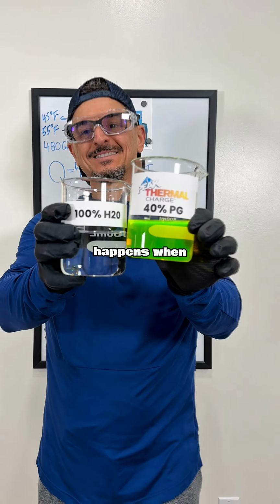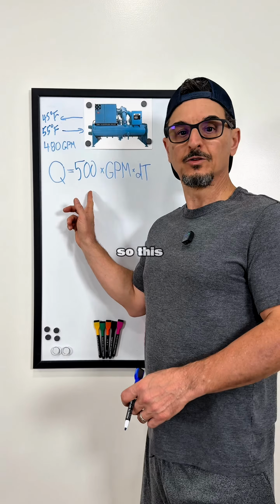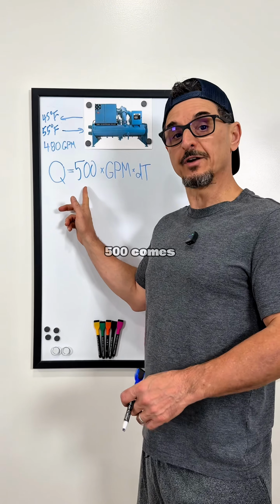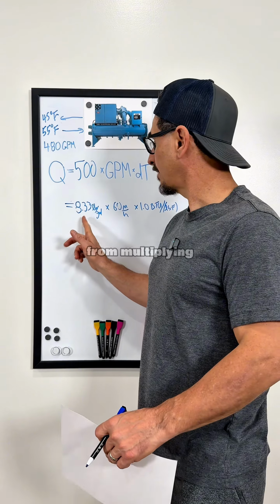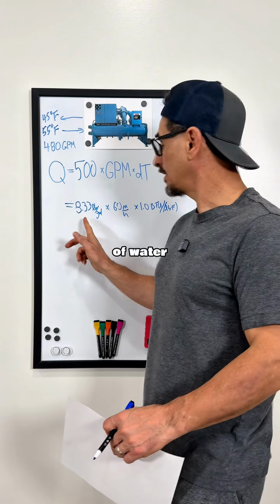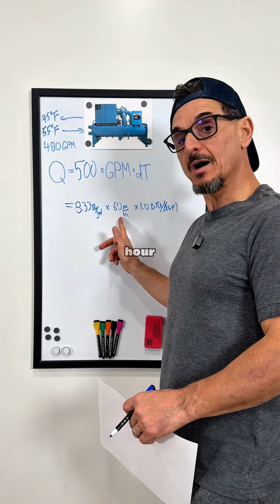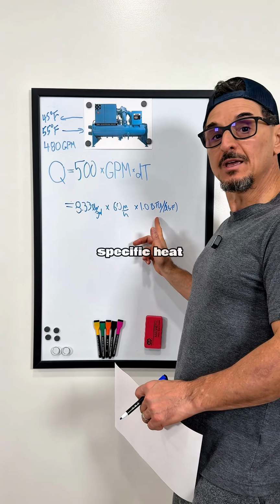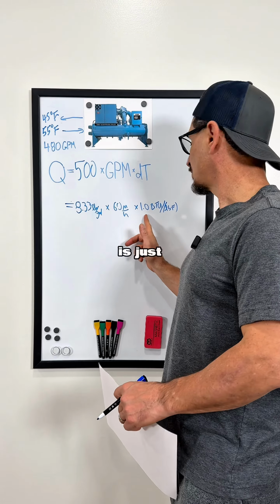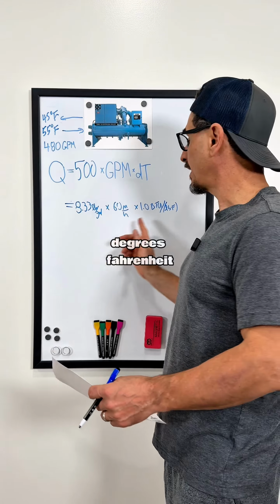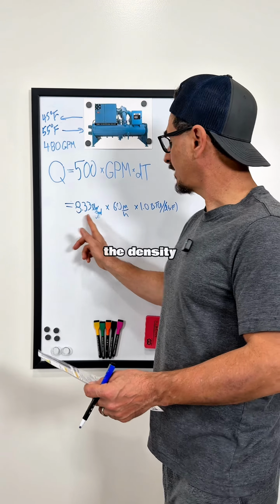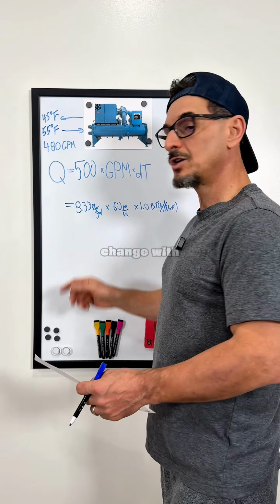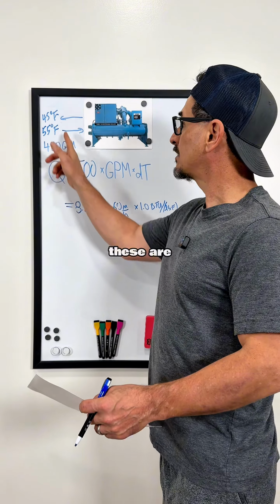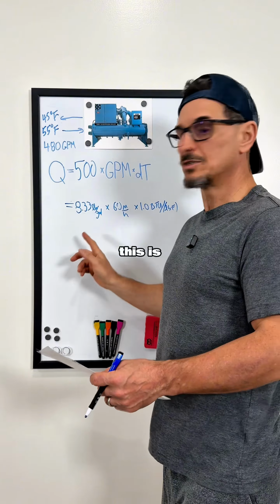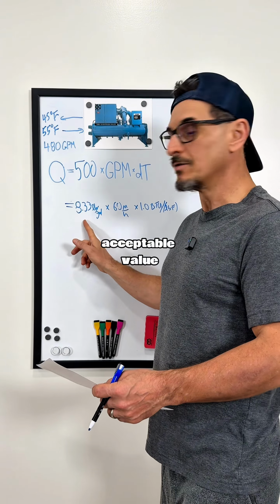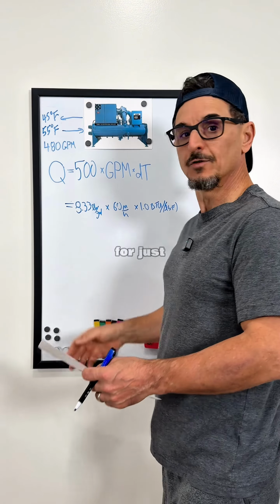Let's look at what happens when we add glycol to the system. So this is where it's important to know where this 500 comes from. The 500 comes from multiplying the density of water times the 60 minutes per hour conversion factor times the specific heat, which in this case for water is just 1 BTU per pound degree Fahrenheit. Now the important thing to note is the density and specific heat do change with temperature, and given these are at relatively standard conditions, this is a widely acceptable value for the density and specific heat of just water.